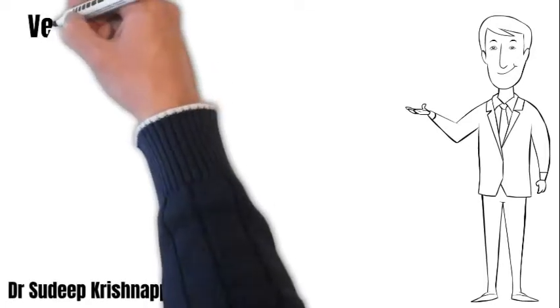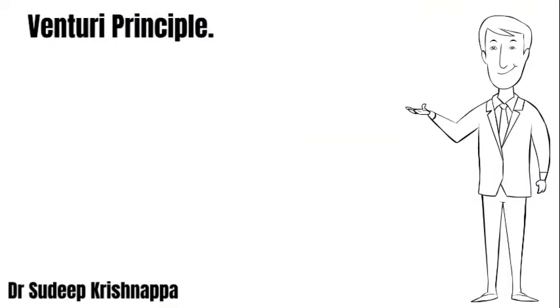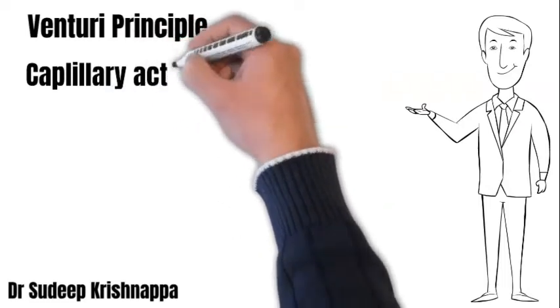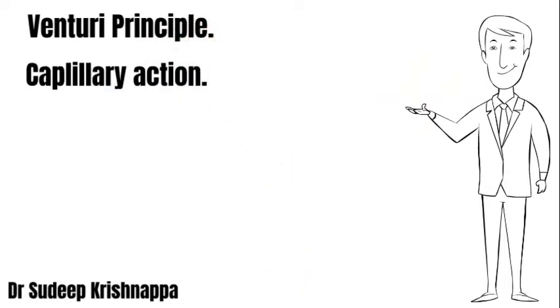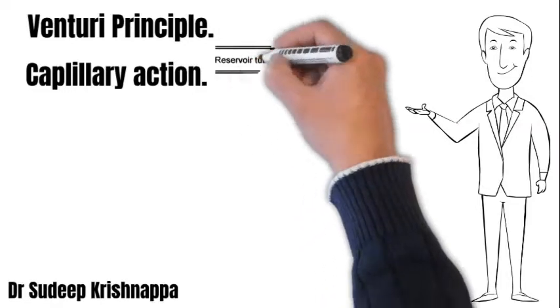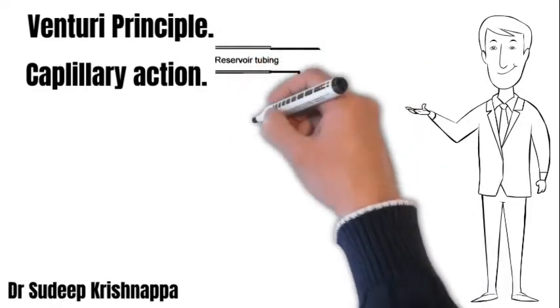The nebulizing chamber is the most important component of this device. This is the site where two key physical principles come into play to make sure the device functions properly. The first one is the Venturi principle and the second one is capillary action. This line diagram represents the internal components of a nebulizing chamber.